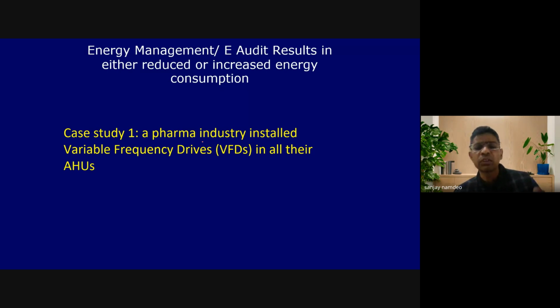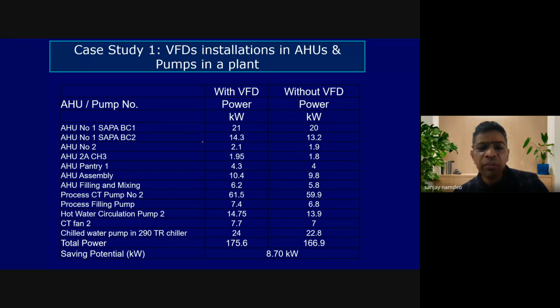So VFD is versatile equipment, which can be retrofitted on common centrifugal or similar kinds of equipment like pumps, compressors, fans, blowers, motors, etc. So this is a very simple way of reducing the energy consumption when the equipment is underloaded. Here is a case study of a plant wherein they installed variable frequency drives on their common equipment. These included some air handling units, some pumps, circulation pumps, chilled water pumps, etc.